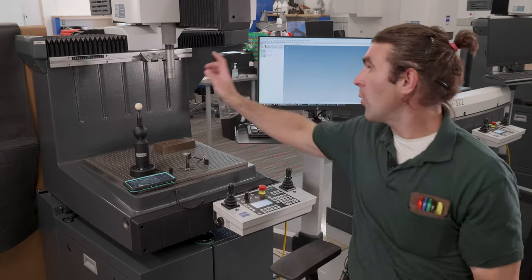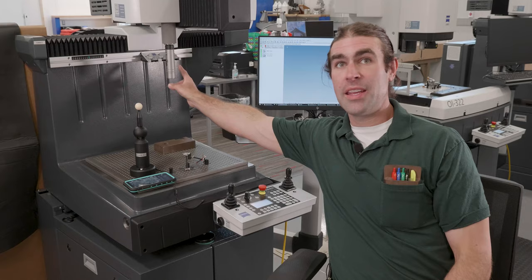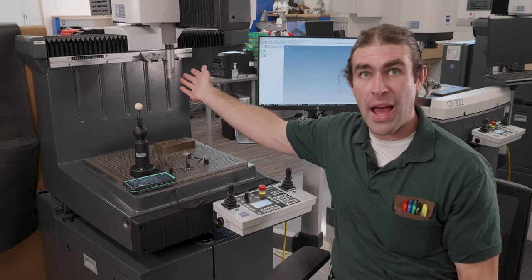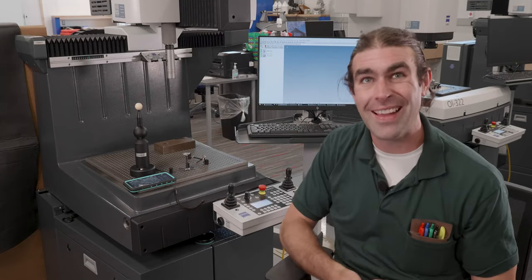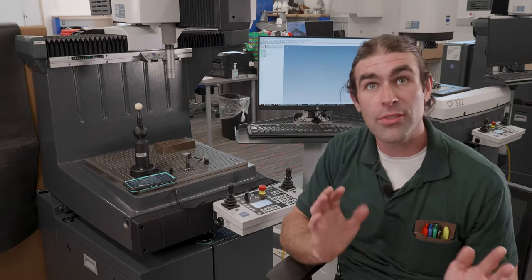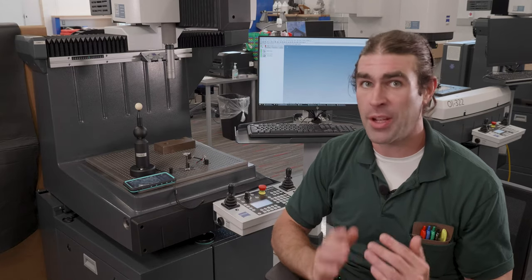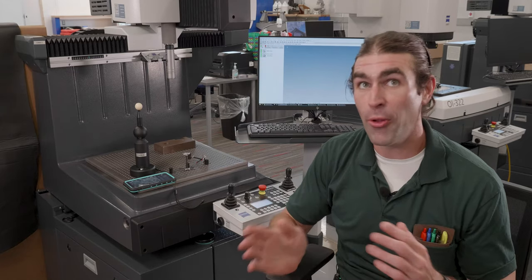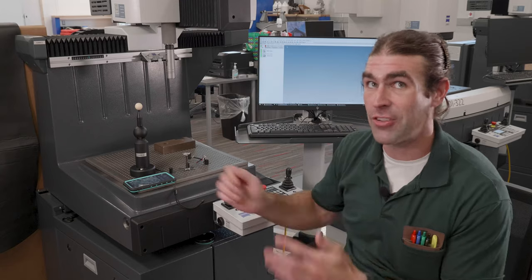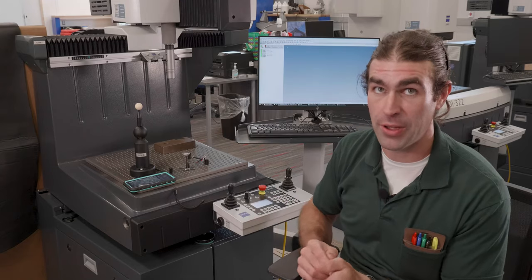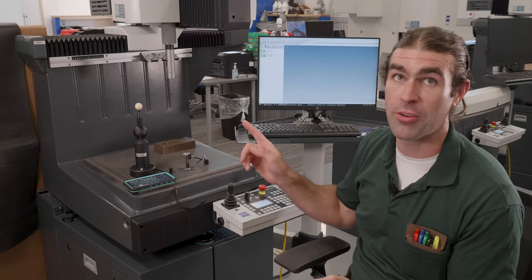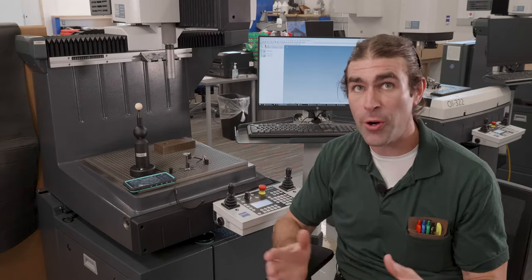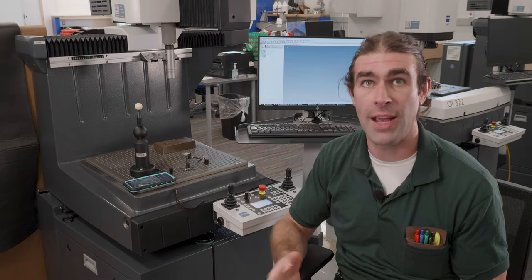So the holder is back here. It's just a little corral for all the stylus systems so that the machine can change them automatically. If you're running a program with multiple stylus systems, you don't have to change them manually. It'll go in and grab them if you set that stylus system holder up correctly.